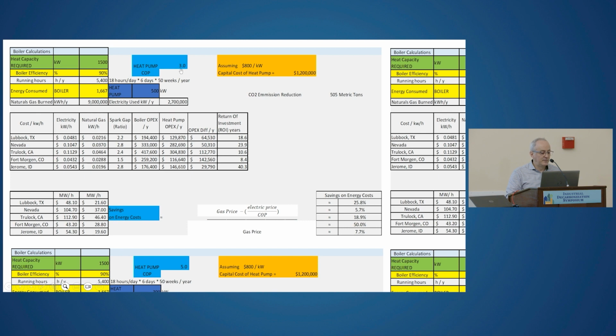Say you get a heat pump COP of 3, you only need 500 kilowatts to make that same 1,500 kilowatts of heating capacity. That means you're only going to consume 2.7 million kilowatt-hours on the heat pump. If we figure the capital cost, between the heat pump and installation, at about $800 per kilowatt, you come around to investing about $1.2 million or $2 million in total.